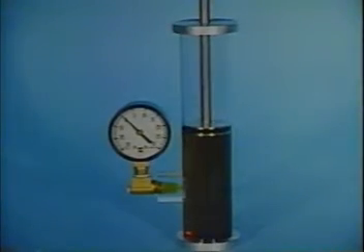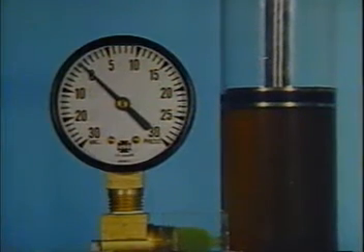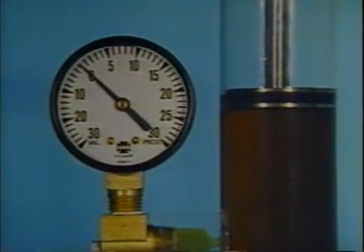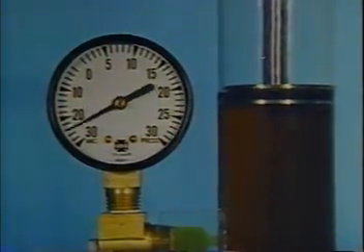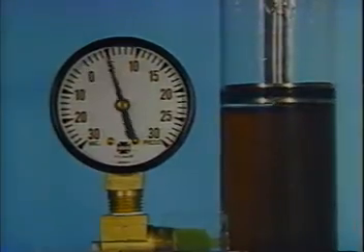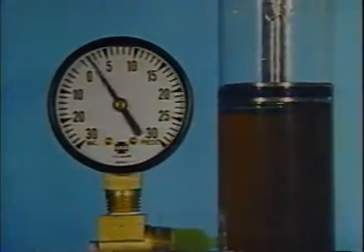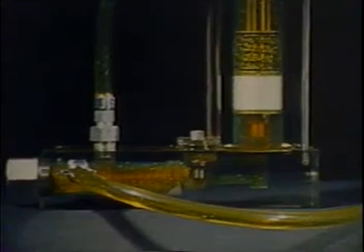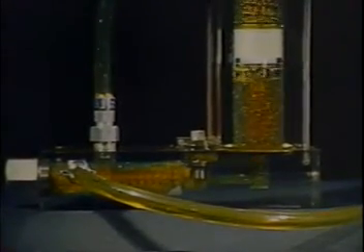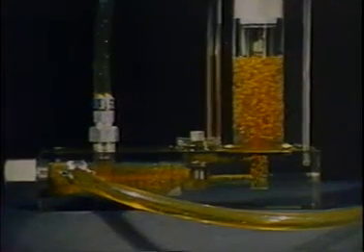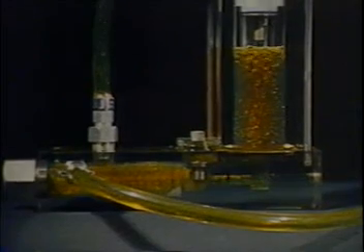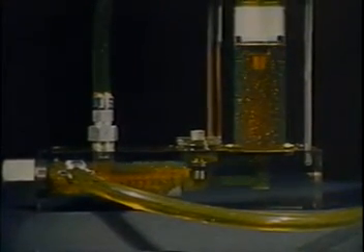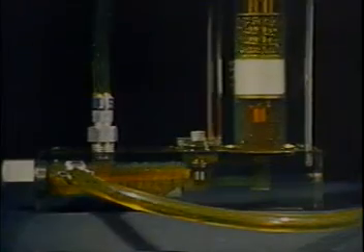Cavitation, demonstrated with a liquid-filled cylinder where the piston is pulled upward away from the liquid level, shows that the cavity is actually a low-pressure vacuum which tends to collapse rapidly, drawing the piston inward before liquid pressure can be developed. The result of cavitation in a double-acting pump is somewhat similar to the effect of entrapped air. Interruption of constant flow occurs at the top reverse. The piston must close the cavity before outward pressure can be developed to push the discharge ball valve open.